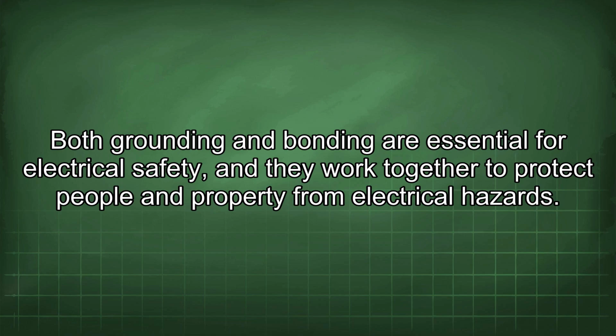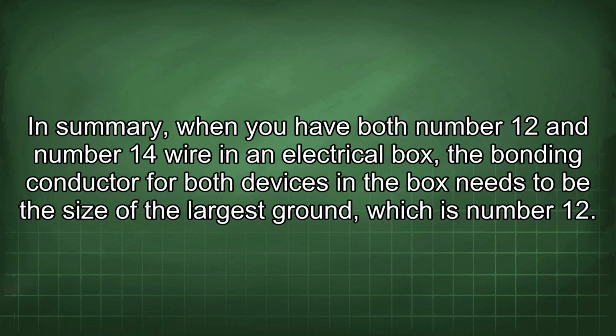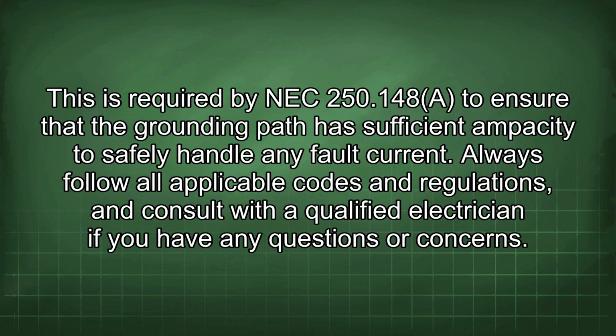In summary, when you have both number 12 and number 14 wire in an electrical box, the bonding conductor for both devices in the box needs to be the size of the largest ground, which is number 12. This is required by NEC 250.148 to ensure that the grounding path has sufficient ampacity to safely handle any fault current. Always follow all applicable codes and regulations, and consult with a qualified electrician if you have any questions or concerns.